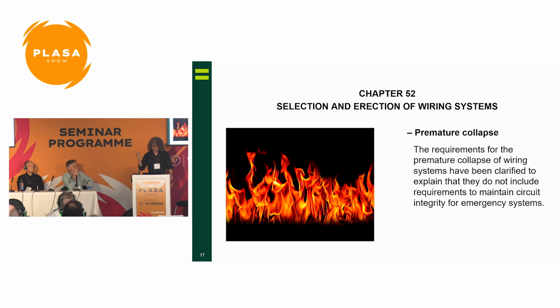But one of the points here, this requirement, it's not about maintaining the integrity of the circuit. This part is purely about ensuring that the cables don't fall, where people need to get out of the building or firefighters need to come in to evaluate what's going on inside. It's about stopping that premature collapse. If the circuits are meant to be there for longevity, to see the building through the fire, so to speak, then that's something else to consider. But that's what's gone in there. This requirement's about premature collapse, and it's not about the integrity of the circuit, although that's something else.